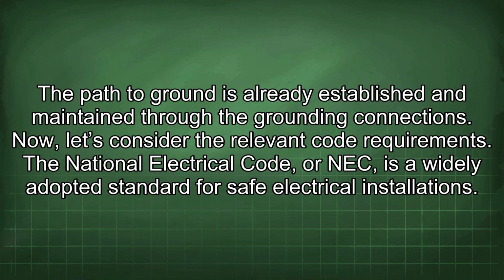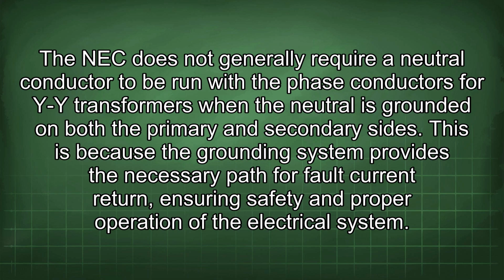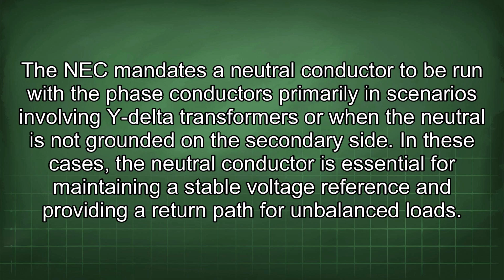Now let's consider the relevant code requirements. The National Electrical Code (NEC) is a widely adopted standard for safe electrical installations. The NEC does not generally require a neutral conductor to be run with the phase conductors for YY transformers when the neutral is grounded on both the primary and secondary sides. This is because the grounding system provides the necessary path for fault current return, ensuring safety and proper operation of the electrical system. The NEC mandates a neutral conductor to be run with the phase conductors primarily in scenarios involving Y-delta transformers or when the neutral is not grounded on the secondary side.